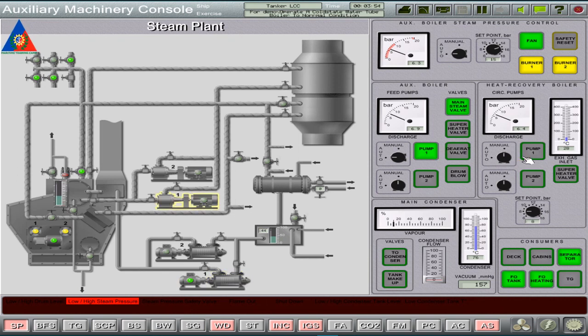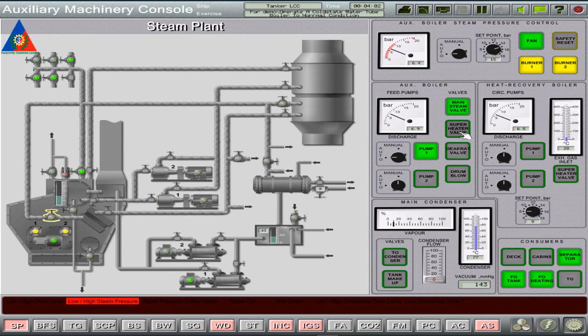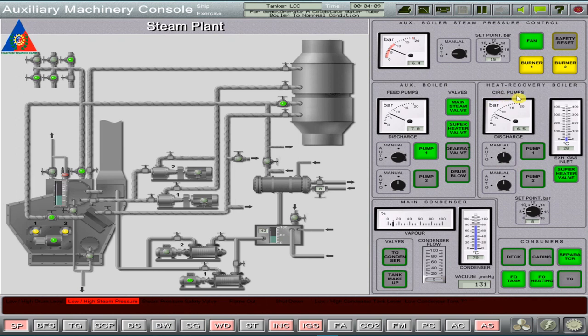Next, open the superheater stop valve for the auxiliary boiler and heat recovery boiler for production of superheated steam for the turbines of the cargo pumps and turbo generator. Do not forget to start the circulating pump number 1 and set it to auto running mode for the heat recovery boiler.